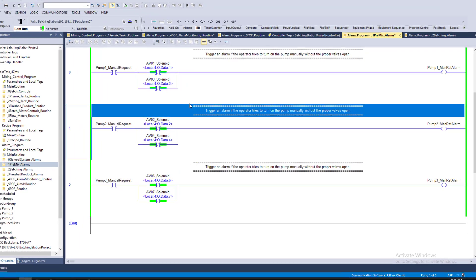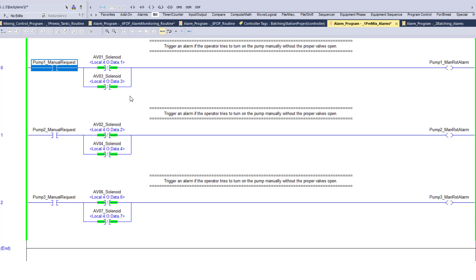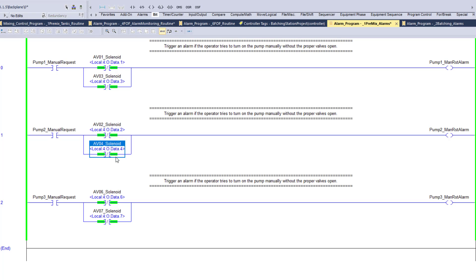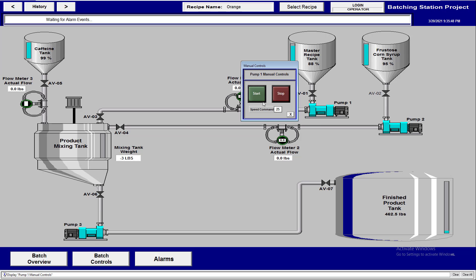I took the liberty of adding some controls to save time — controls we know we need. For instance, if the operator turns on the manual control for a pump but does not turn on AV01 or AV03, it triggers a pump manual request alarm. The same applies for pump 2: if AV02 and AV04 are not on, it triggers and holds that alarm just like we showed. I don't currently have alarms triggering in the alarm banner because nothing is programmed yet, but I want to show that alarm actually working.